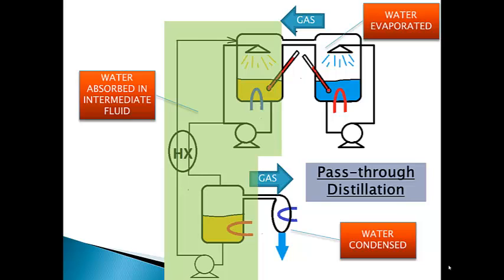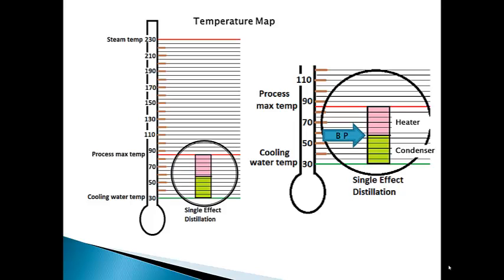Let us now see how pass-through distillation compares with ordinary distillation with respect to temperatures. In this chart, important temperatures are shown for a particular plant operating a single-effect distillation. The maximum available temperature from the steam supply is 230 C. The cooling water has a nominal temperature of 30 C. The product being distilled is temperature sensitive, and a limit of 85 C has been set for the process. The temperature difference between the 85 degrees C subatmospheric steam and the 30 degrees C cooling water is shared between the heater and the condenser. If they are balanced in size, each will have a delta T of 27.5 Celsius degrees.